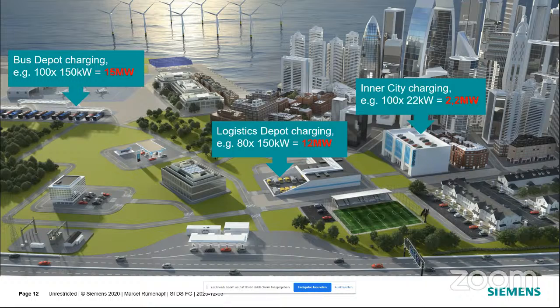We would have a similar situation with vans or trucks for logistics companies, shown here in the center. Power ratings for the chargers, 150 kilowatts, is common today. Depending on the number of vehicles in the depot, we see the total power demand for the installation, but also bigger quantities of AC chargers for cars. If we have a whole parking garage with many vehicles connected, charging at full power of 22 kilowatts through AC, this can already result in the megawatt range of grid connection.